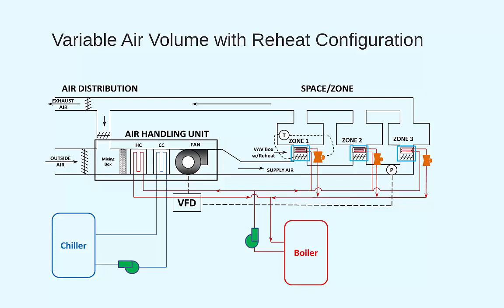So let's see how this all works. Back at the air handling unit, we can modulate the cooling coil's control valve to track on a discharge air temperature of about 55 degrees Fahrenheit. So no change there. We have seen this before. Now we have cool air in the supply duct available to provide cooling to the various zones. At each zone, you again have a temperature sensor which measures the space temperature and sends that information to a controller located in the VAV box.